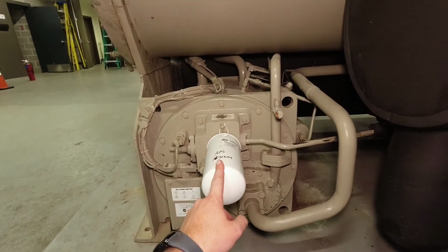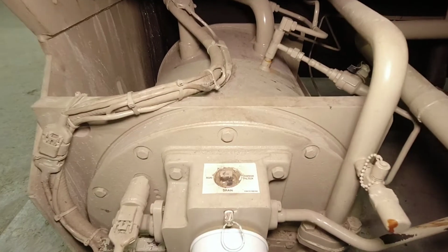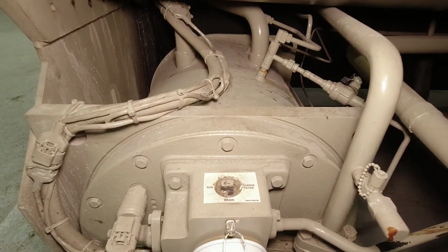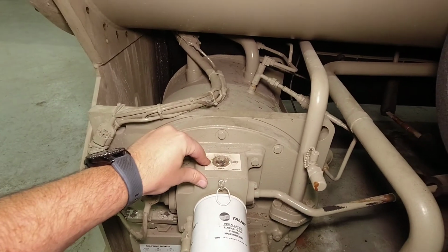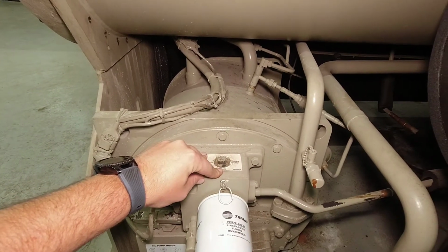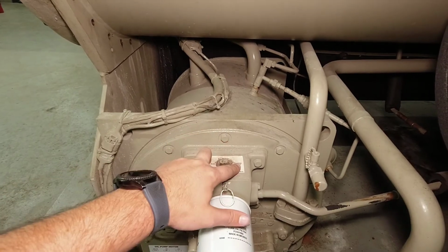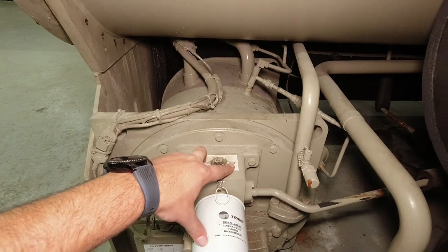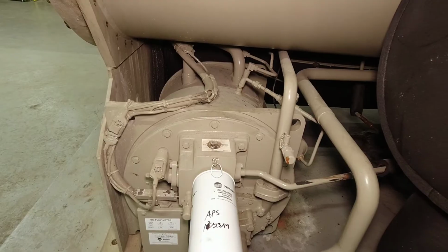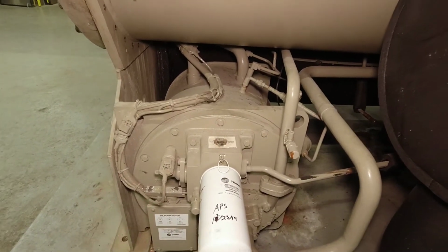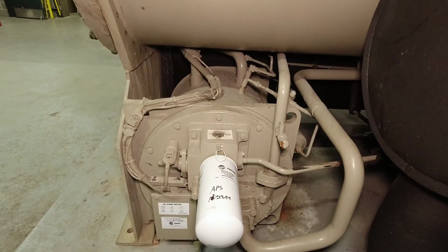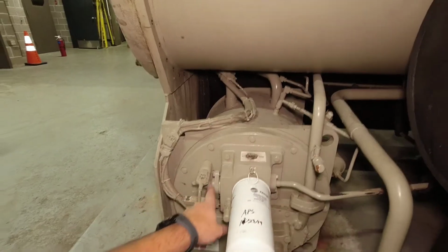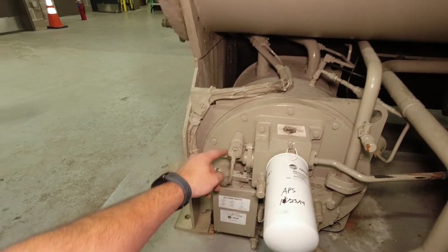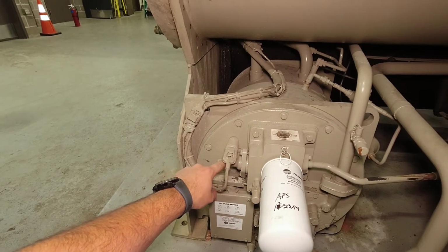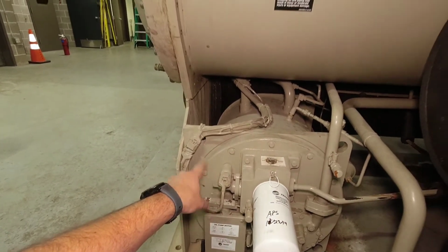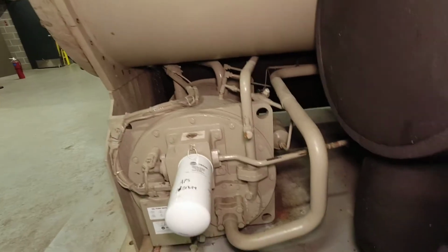This is your oil filter. You do have a filter adjustment there, so this is for the run cycle. Whenever you go to change the filter, you have to drain it, and then you move this over to the change filter setting, and you can spin this canister filter off and spin a new one on really quick, without having to take the whole machine down. This is your oil pressure regulator here on the side, so if you need to make any adjustments to your oil pressure, it's not regulating properly, that is where you can do that.